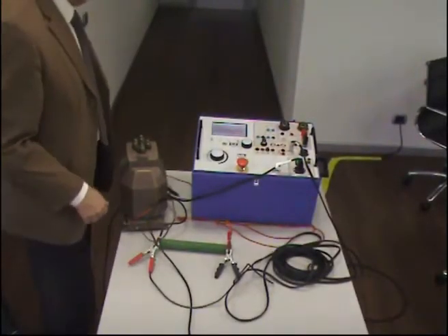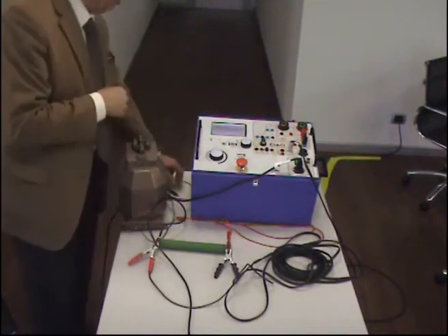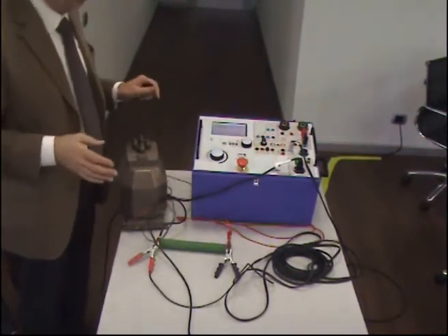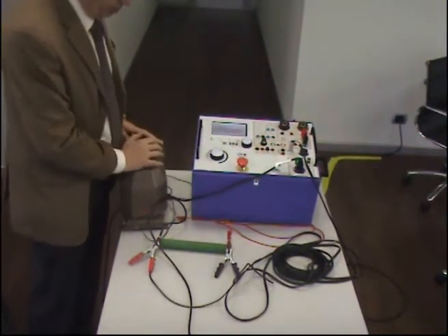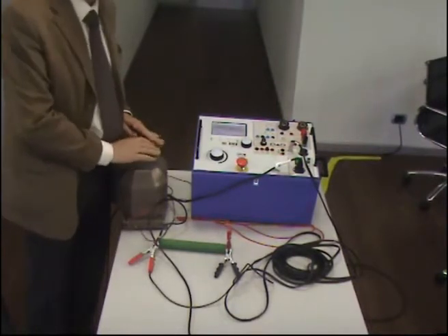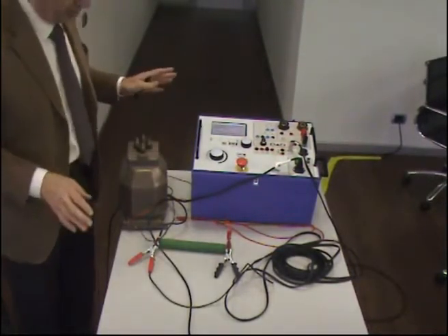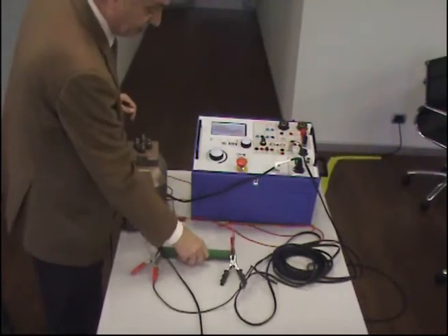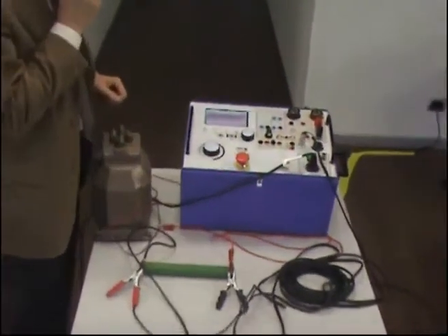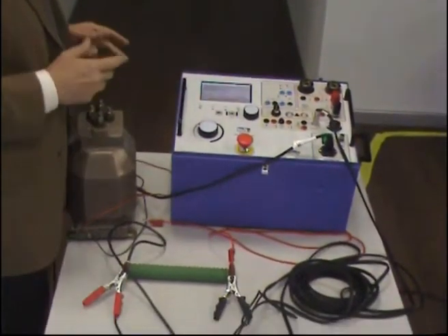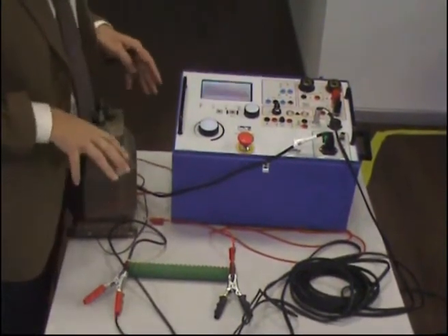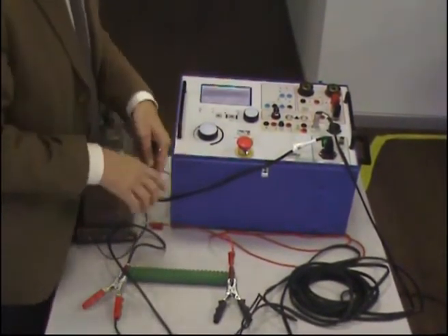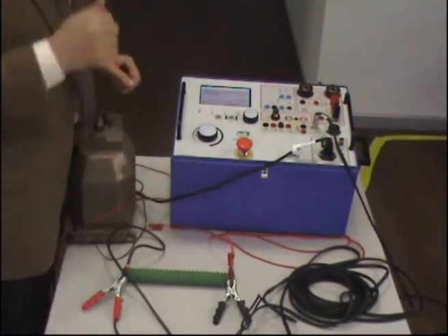The next selection is burden secondary side. Burden secondary side means that we don't inject current into the transformer, but into the burden itself. So this is my resistance that is simulating the burden. What we do in this test is inject a current directly into the secondary connection cables.